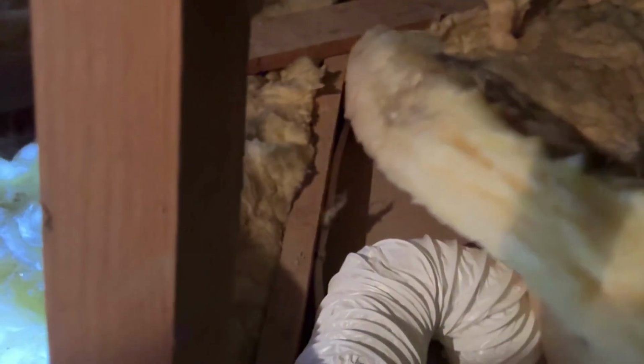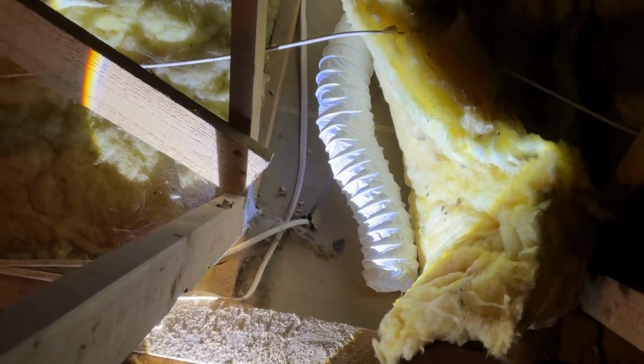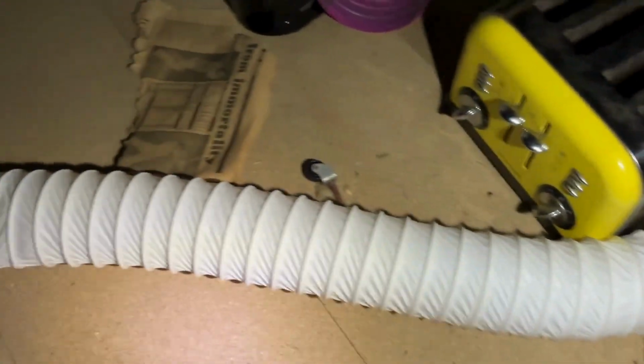But same as the previous one, I can hear this noise, and there's the ducting, and it is discharging directly into the loft space. So again, it's not going to be working efficiently down in the kitchen, and it is going to be ducting and venting some of that warm, moist air into the loft. In the longer term, this can cause issues with condensation in the loft space, and eventually it could lead to other issues like woodworm.